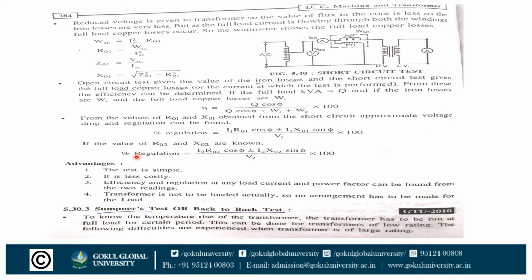Now advantages of this test. First one is the test is simple. Second one is it is less costly. Third one is efficiency and regulation at any load current and power factor can be found from the two readings. And fourth one is the transformer is not to be loaded actually, so no arrangement has to be made for the load.